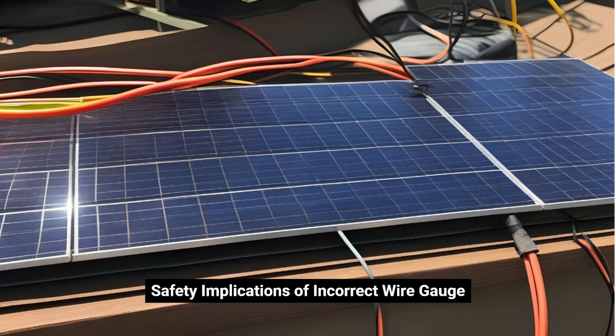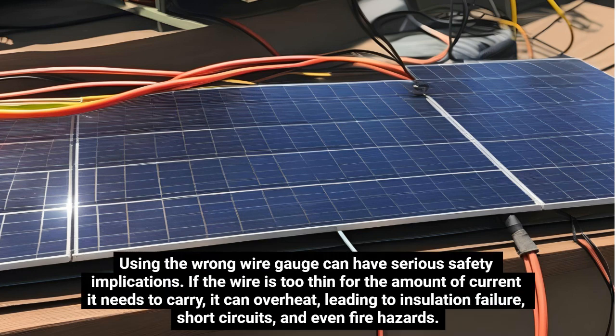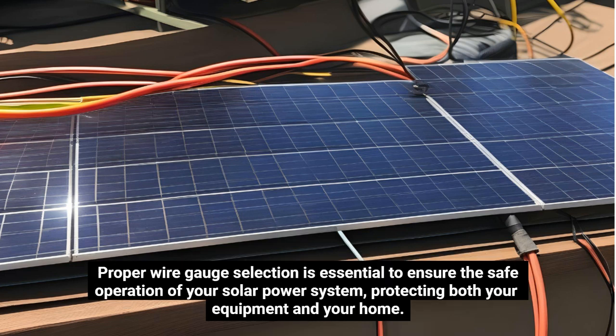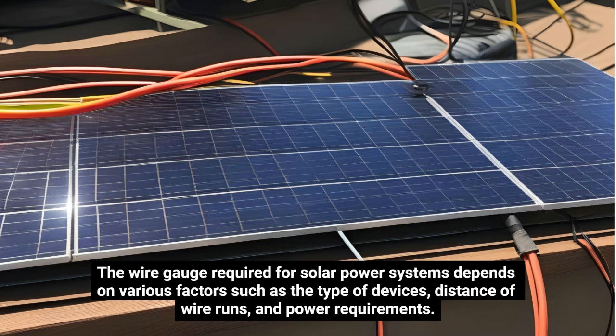Safety implications of incorrect wire gauge. Using the wrong wire gauge can have serious safety implications. If the wire is too thin for the amount of current it needs to carry, it can overheat, leading to insulation failure, short circuits, and even fire hazards. Proper wire gauge selection is essential to ensure the safe operation of your solar power system, protecting both your equipment and your home. The wire gauge required for solar power systems depends on various factors such as the type of devices, distance of wire runs, and power requirements.